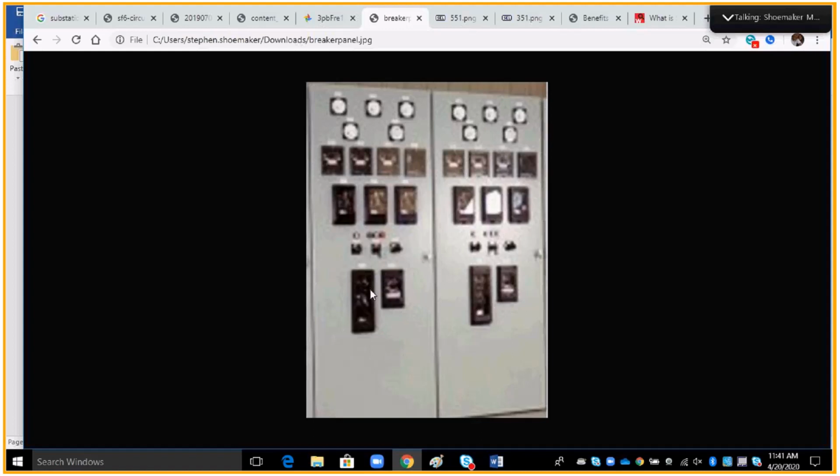I's and T's, instantaneous and timed, and simply in here is a disk that's turning at a certain speed because of time, and it gets to a point at the end, and you can see it on the disk, there's actually a term that says lockout. Well, when it's at lockout, I'm finished. I'm not going to do any more without some type of human intervention to get power restored. This is a huge safety feature. So if I want 1 instantaneous and 2 timed, I know after the second time, as far as my circuit is concerned, there's a fault in my circuit that's just not going away.